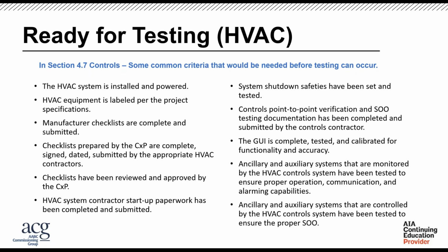And a lot of times there's the urge to test the equipment and the controls separately, and they function as one. And when that happens, as the schedule gets pushed, controls might not come until after the building is in operation. So one of the big things is to focus on the controls, that we try to hammer that during the kickoff meeting and get that coordination as smooth as possible and make sure we're all asking the right questions. And some of the biggest things are ensuring the design sequence matches the control sequence.